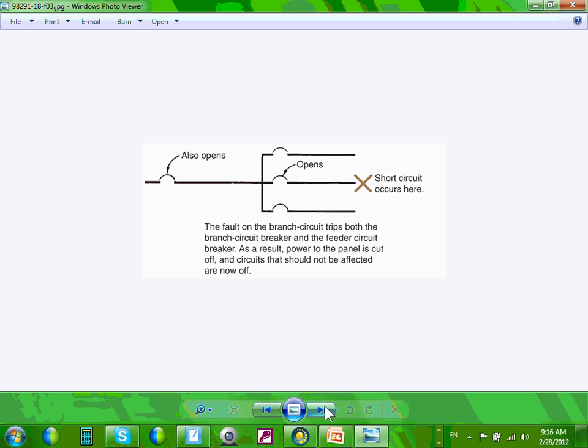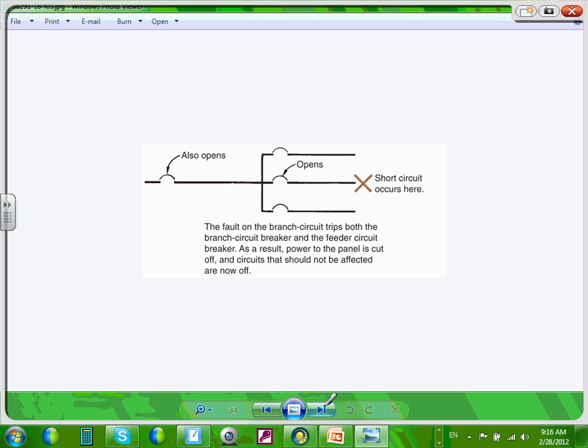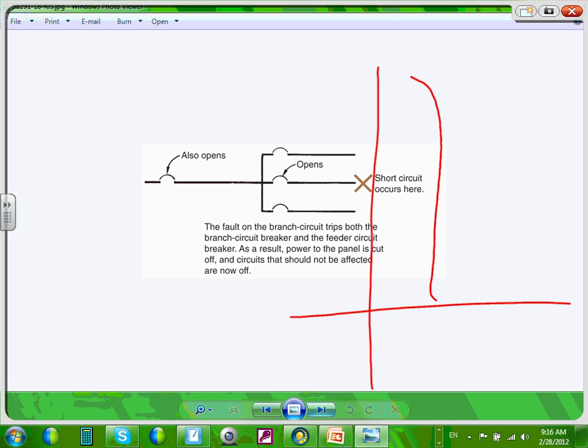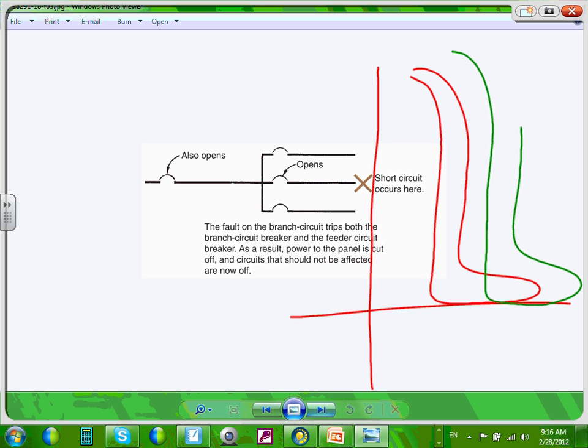Okay, the second thing, guys, is overcurrent coordination. If you have overcurrent coordination, here's what I'm going to show you, a curve for two circuit breakers. Here's one circuit breaker, and the other one is another circuit breaker that sits something like this. This is the time, and this is the current, I. And as I said yesterday, right in this zone here, this is fully coordinated except where? Except right in this zone. Can you guys see that this zone here is miscoordination?